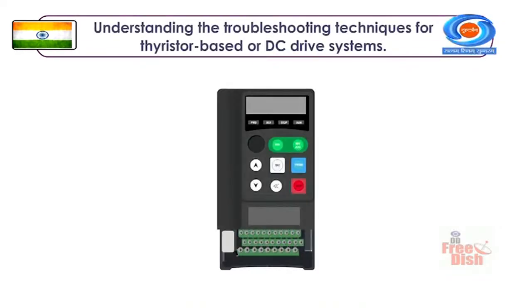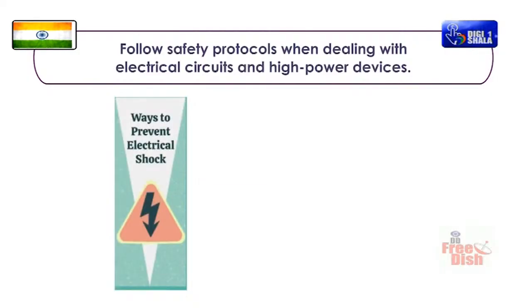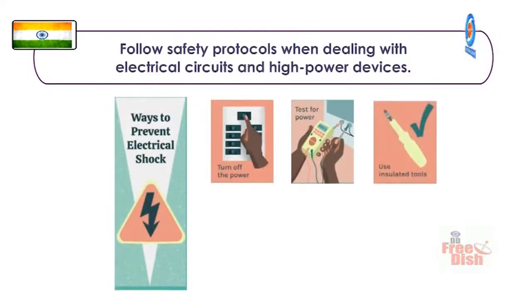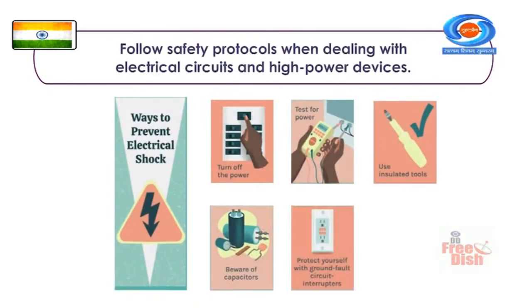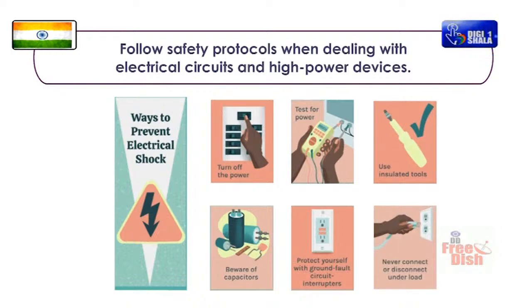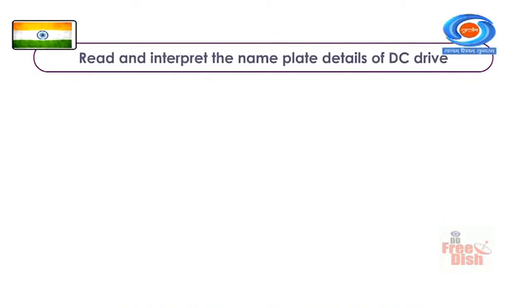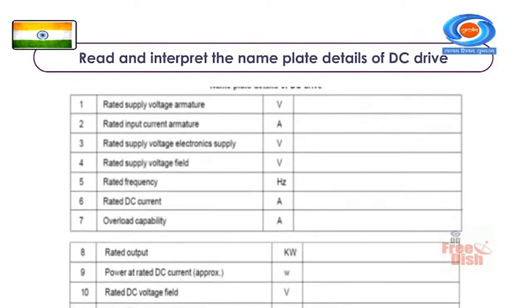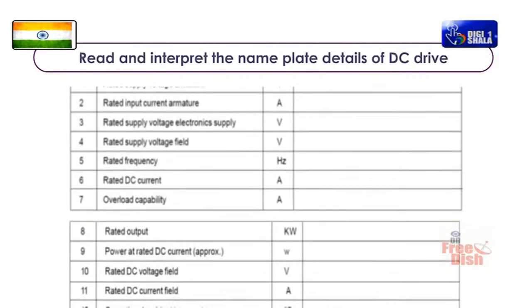Familiarize yourself with troubleshooting techniques for thyristor-based or DC drive systems. When handling electrical circuits and high-power equipment, you should be cautious and adhere to safety protocols. You will use the thyristors or DC drive to begin our attempt at speed control of a DC motor. Our first task is: read and interpret the nameplate details of the DC drive.